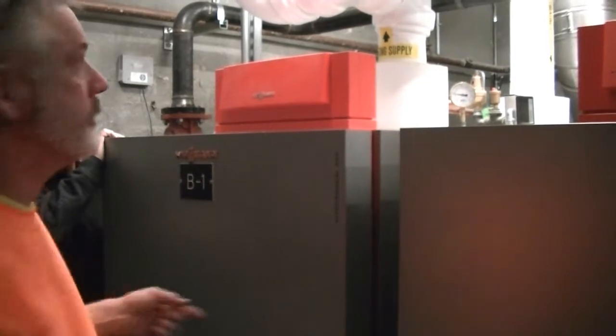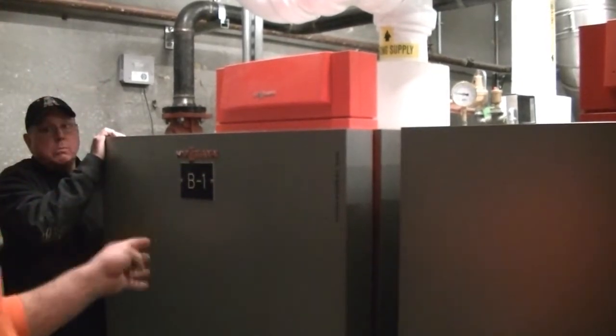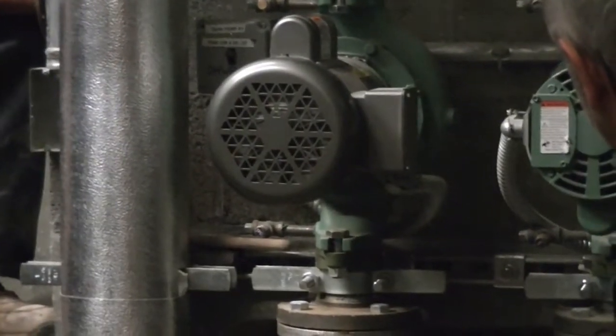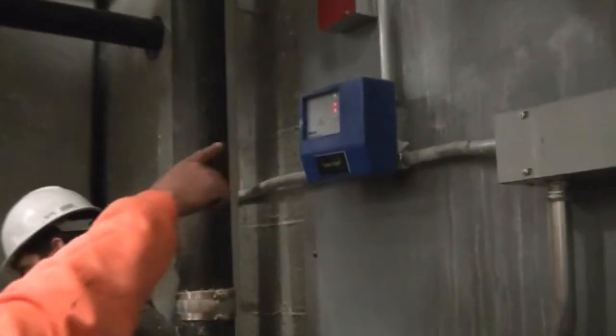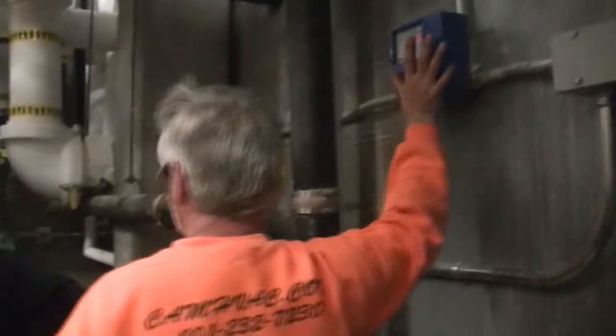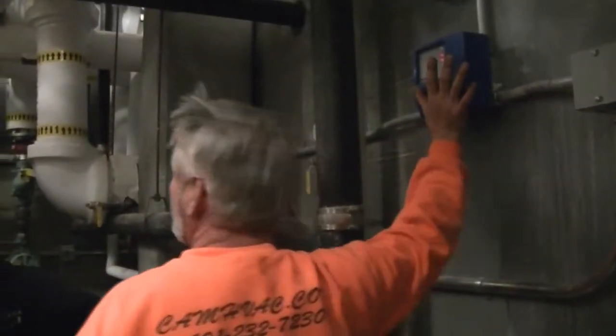Domestic hot water. The boilers control the domestic hot water. Over on the wall over here are your 2 zone pumps. You take the boiler water and send it over to the heat exchangers in the domestic hot water tanks. Okay? They only run when there's a call for domestic hot water. I tripped that out by hitting the starters, marked here DWH, shut it down. Okay, it was in alarm. Okay? This is something that your control vendors can go over with you once we're done.